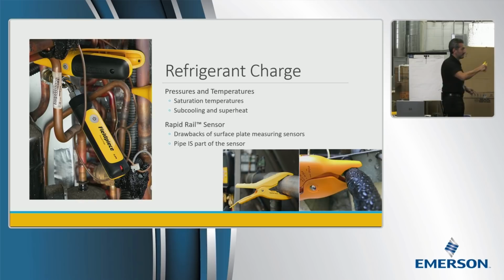Now, what if I put it onto a piece of pipe where there's just a lot of crap on there and there's not good contact with the copper? Both of you are correct, right? So I put it onto a pipe and I get a double beep and it's yellow. Crap. The first thought is, well, this clamp sucks because I don't get a temperature reading. But what we don't realize sometimes is we don't want the reading in that location anyway, because it's not going to be as accurate a representation of what's going on in the pipe because of insulation, dirt, debris, whatever the case may be.